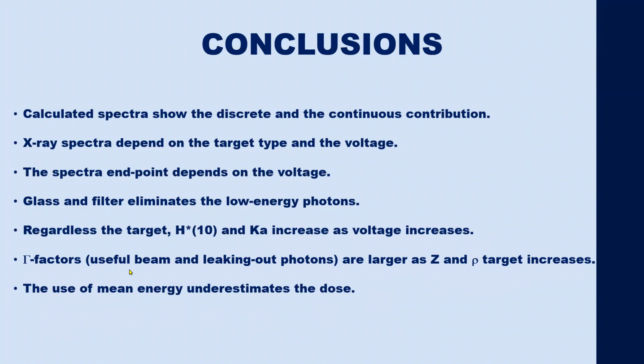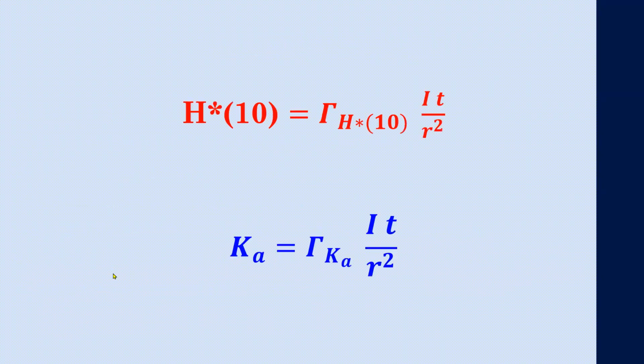What is the advantage of using the gamma factors? Because in a very simple expression, the gamma factors for ambient dose equivalent or air kerma can be used to obtain the ambient dose or the air kerma, only knowing the current of the X-ray tube and the time that the X-ray beam is on, and we only need to define at what distance from the focal point we want to know the ambient dose equivalent or the air kerma.